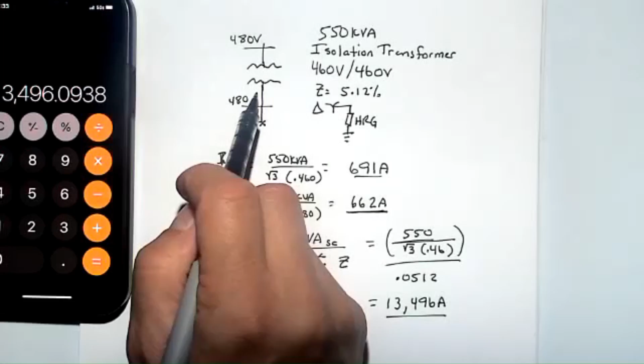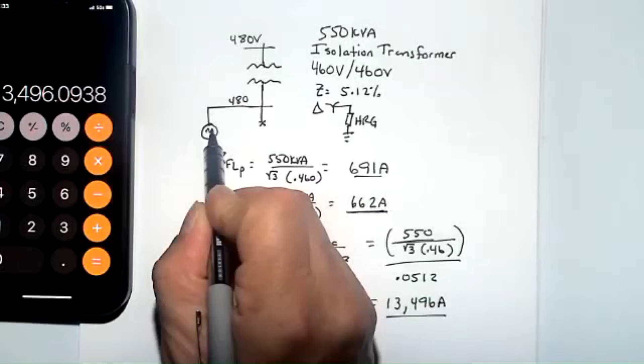Because remember, we ignored our primary impedance of our source above that. And a lot of times in this case, especially where you use an isolation transformer, the transformer upstream of this might not be very small or very big. In fact, it might be closer to the range of this transformer. So we do have to take that into account sometimes in a more formal study. But again, it's going to knock that number down. Also, if we have motor contribution here, that motor contribution could increase the fault current for a short period of time during fault conditions. So again, these numbers are estimates.